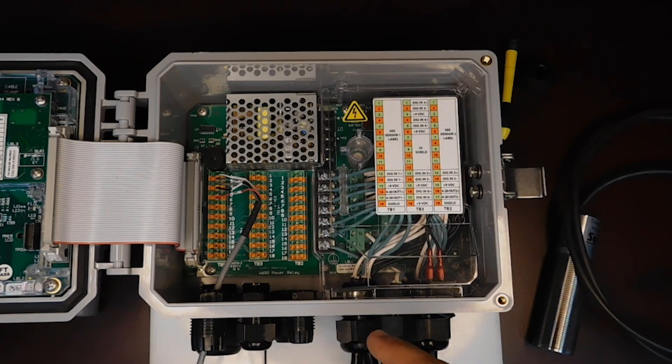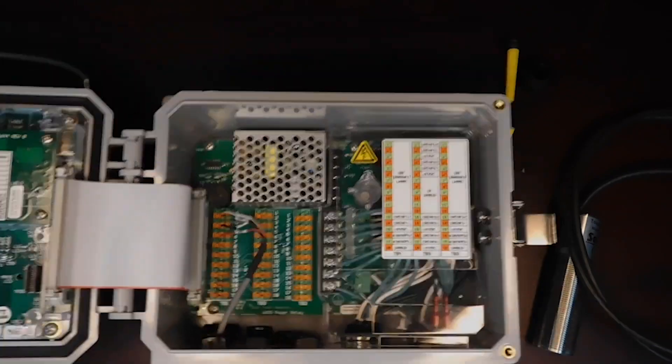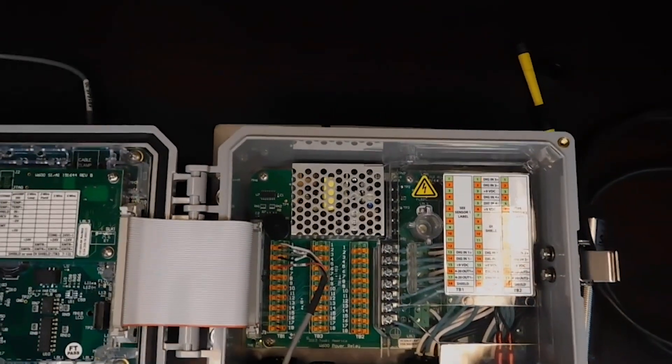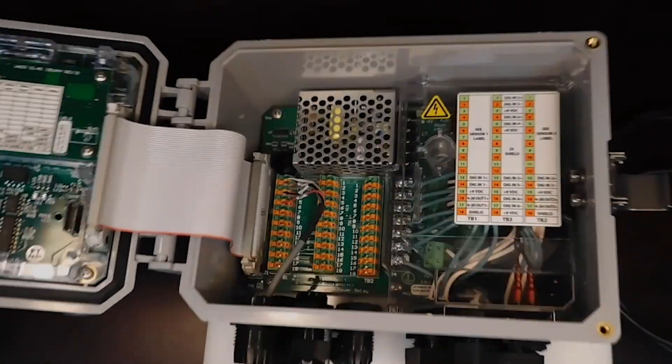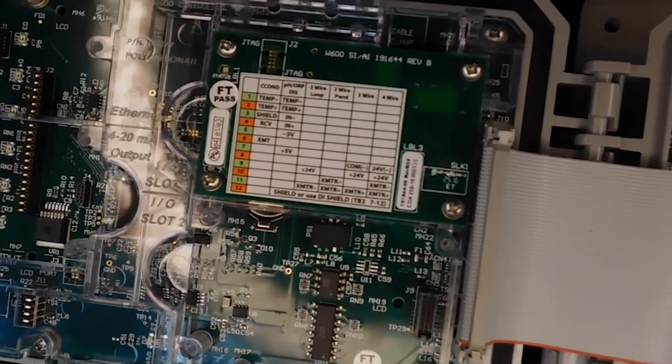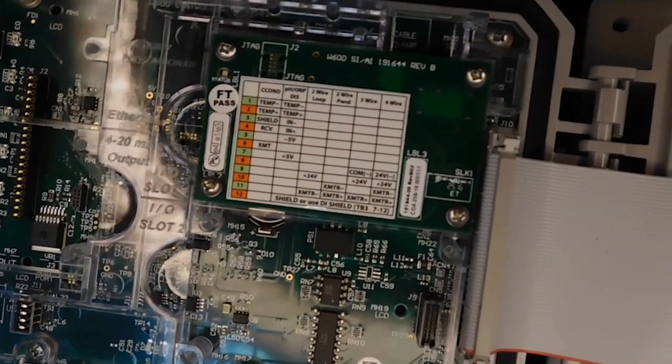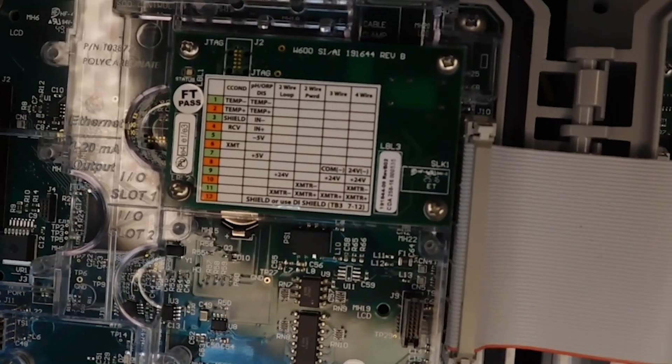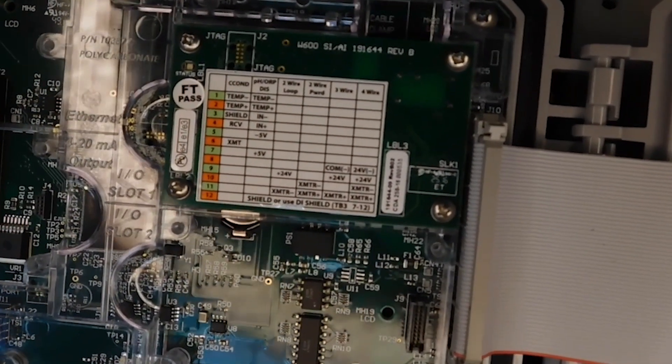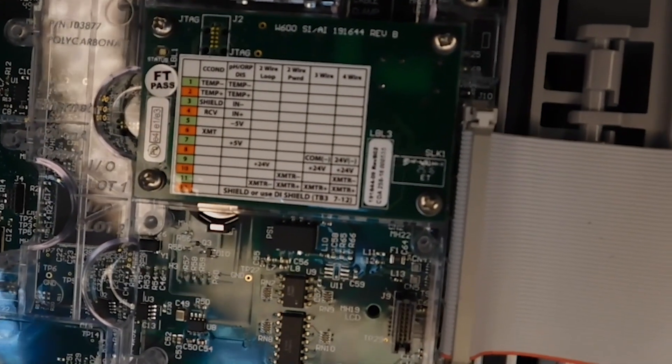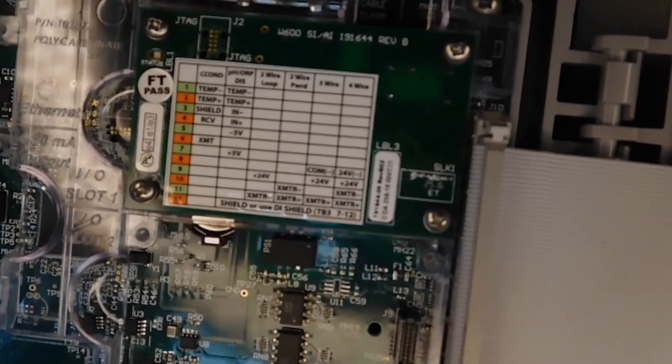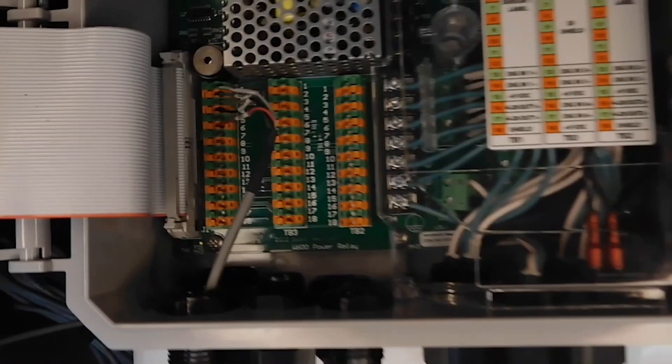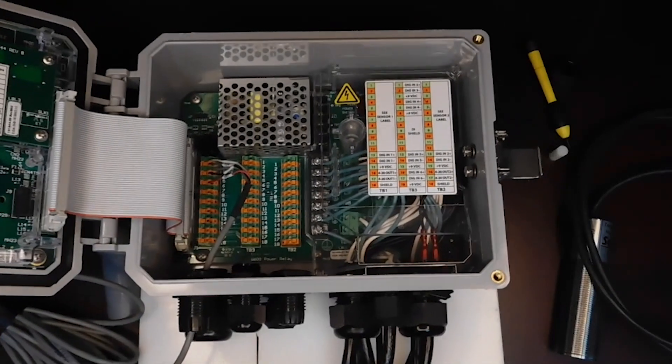We are going to be wiring this into sensor one, so we're going to take a look at the sensor one card. We know that this device is a 4 to 20 milliamp input, and we know from the manual that it is a three-wire device. So we are going to follow the column that says three wire and use the wiring that's specified there.